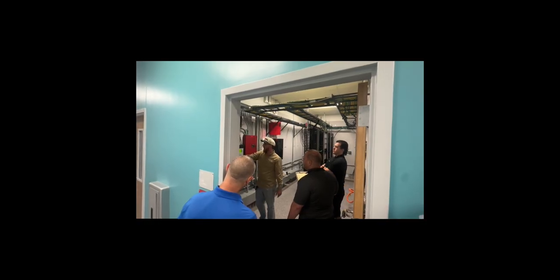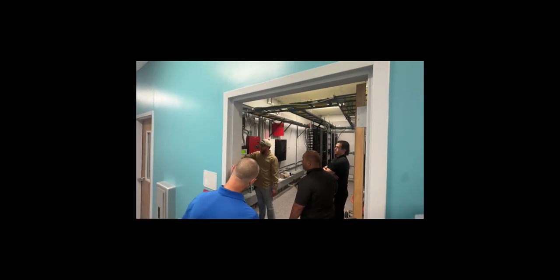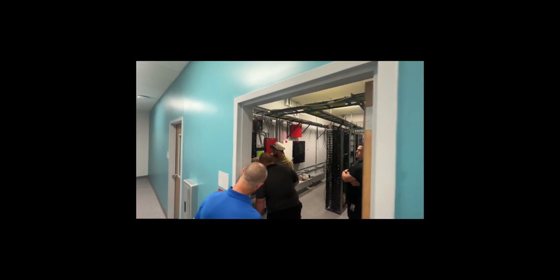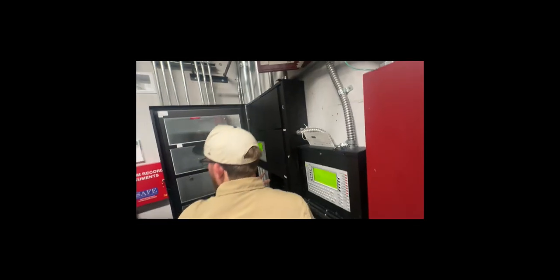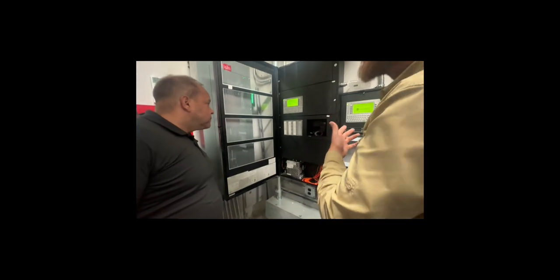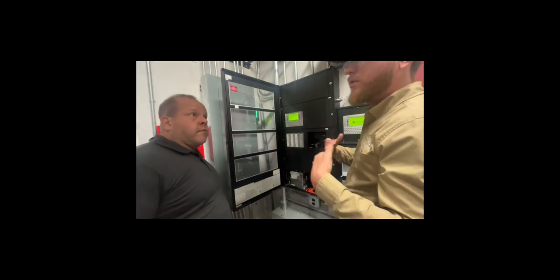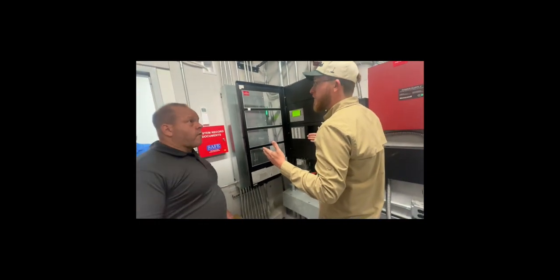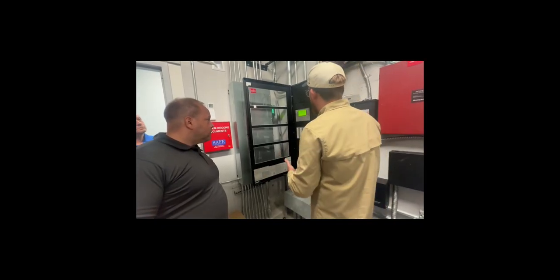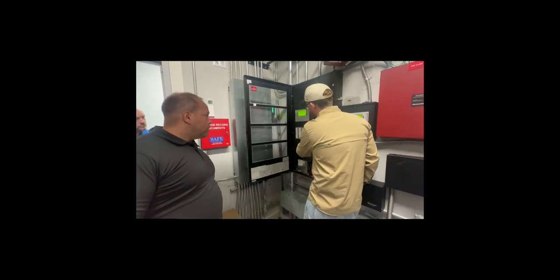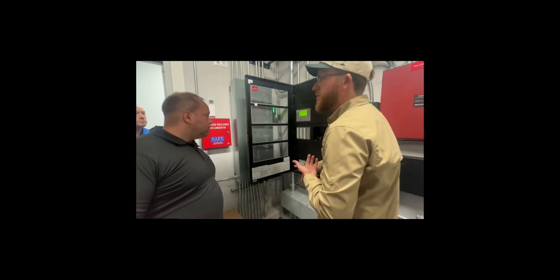Your voice evac panel right here, we have descriptions right here. These are your zones. So you have your main building. What is this? So you're disabled for your speakers, and then you have your relays. Your relays are for your air handlers and your doors. So you have smoke doors that close upon an alarm. So if you're doing any testing, you got maintenance or anything from the county coming out, you can disable relays, which will then stop those functions from happening.